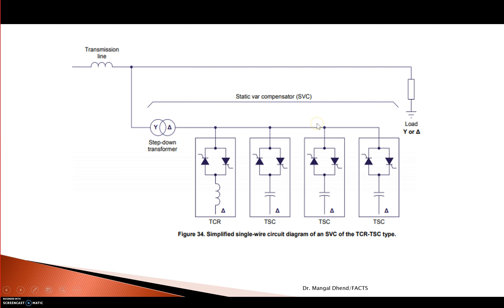Consider the same example with 3 capacitor banks — 3 TSC branches and only one TCR. When the system requires 40 KVAR to be absorbed, TCR can produce 40 KVAR, and all TSC branches can be switched off by thyristor control. That was not possible in the FC case — in FC there was no possibility of switching on and off, but here TSC can be made off, and TCR will produce 40 KVAR to absorb.